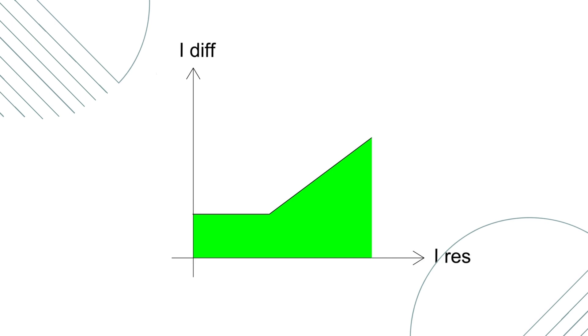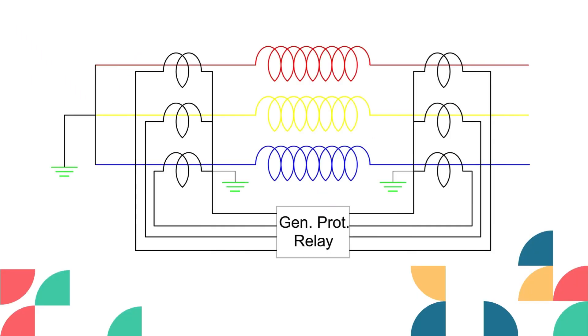This is the concept of biased and percentage differential protection. If we plot the restraining current and differential current, the green zone will be the safe zone. For any value of restraining current and differential current within this zone, the differential relay will not operate. But outside this zone, the relay will sense a fault in the stator winding and close the trip contact. We can change the slope by changing the turns of the restraining coil. That's the story of the electromechanical relay.